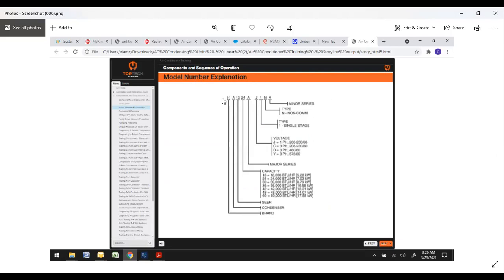Here's an explanation of the model number. Your first letter is going to be the brand. In this case, R for Rheem. If you're Sure Comfort, it'll be an S. Ruud, it'll be U. Your A stands for air conditioning. The next two digits are your SEER, so it's an RA13, 13 SEER. Next one is your capacity, 24, 2 ton.